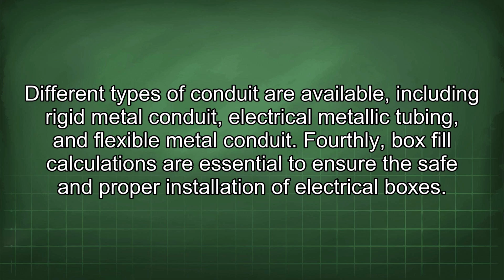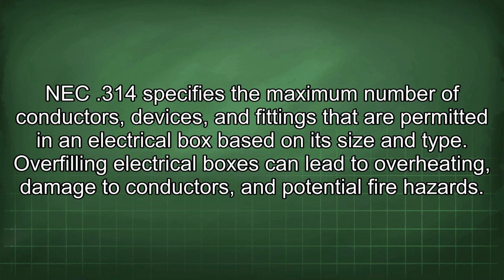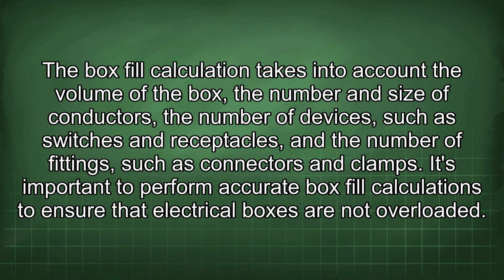Fourthly, box fill calculations are essential to ensure the safe and proper installation of electrical boxes. NEC 314 specifies the maximum number of conductors, devices, and fittings that are permitted in an electrical box based on its size and type. Overfilling electrical boxes can lead to overheating, damage to conductors, and potential fire hazards. The box fill calculation takes into account the volume of the box, the number and size of conductors, the number of devices, such as switches and receptacles, and the number of fittings, such as connectors and clamps. It's important to perform accurate box fill calculations to ensure that electrical boxes are not overloaded.